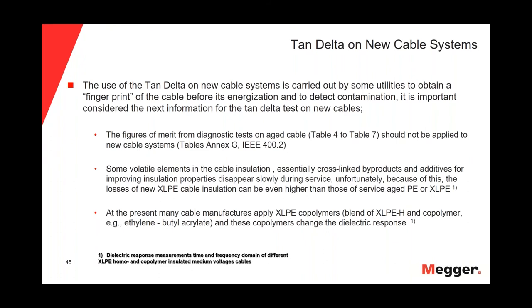The second point is that there are some volatile elements in the cable insulation — essentially cross-linked by-products and additives — that will disappear slowly during service. Because of this, the losses of new XLPE cable insulation can be even higher than those of service-aged PE or XLPE insulations. The last point is that at present, many cable manufacturers apply XLPE co-polymers — to distinguish between homopolymer and co-polymer: an XLPE homopolymer is a pure polyethylene, while an XLPE co-polymer is a blend between XLPE and another co-polymer material such as ethylene butyl acrylate.